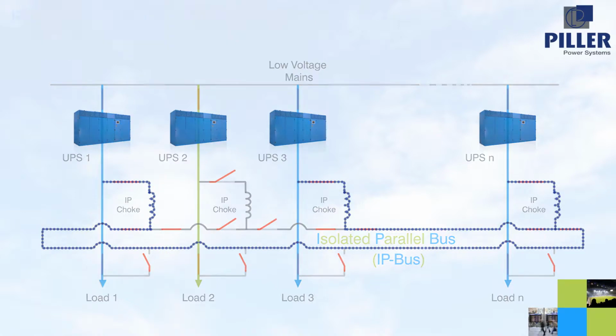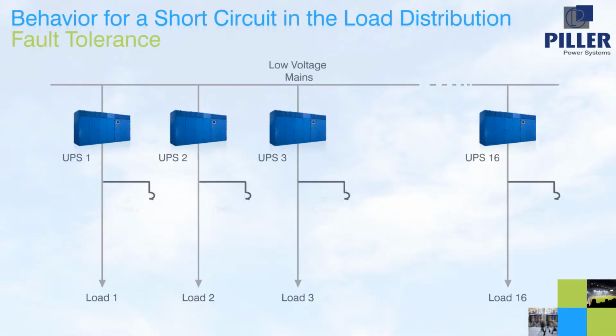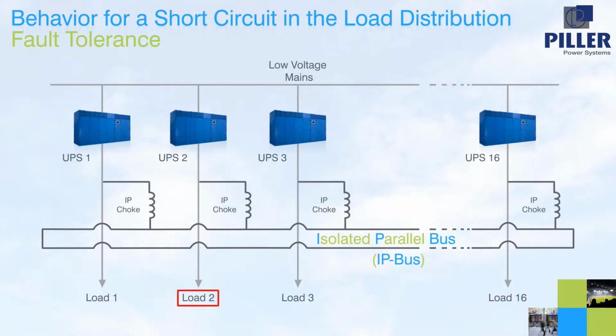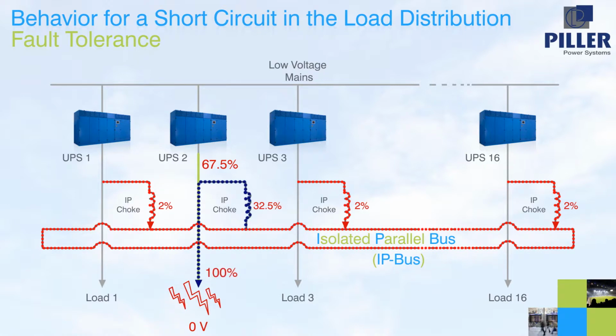As with all schemes, the highest risk of a short-circuit fault lies within the load distribution network downstream of the UPS. A short circuit at the load in any system will reduce the load voltage to zero, and in the case of conventional parallel redundant solutions will often cause a complete loss of load. With an isolated parallel system, healthy loads are separated from the fault as follows. Most of the fault current is provided by the directly connected UPS, and the balance by only a small contribution from each of the other UPS. Accordingly, loads connected to the other UPS are not affected.